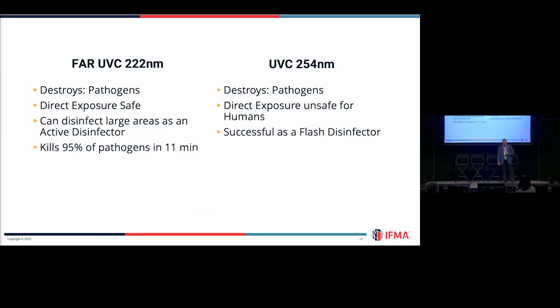So FAR UVC, the 222 nanometer, it'll destroy pathogens. Direct exposure to humans is safe. It can disinfect large areas as an active system, and it'll kill 95% of the pathogens in 11 minutes. It's pretty quick cleaning.